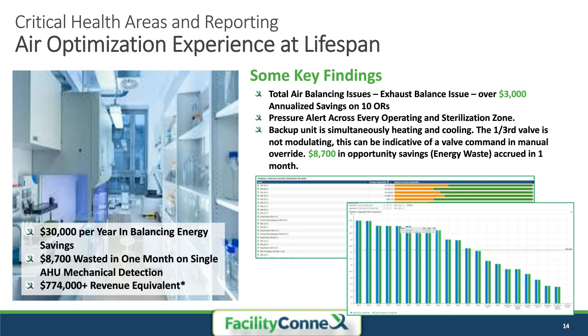That's a huge amount of energy waste. In fact, this year alone we've saved almost close to $40,000 in energy savings. By the way, fixing that simultaneous heating and cooling was a quick 5-minute change on the BMS system, and now the facility engineer is saving $8,700 in this environment.